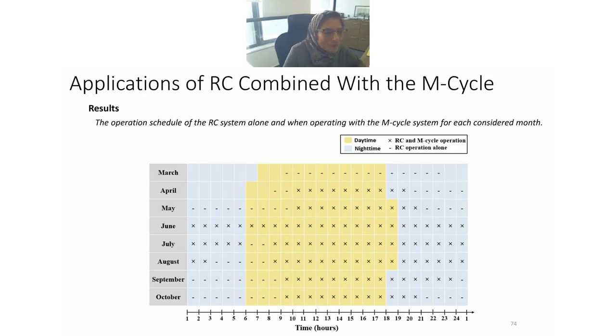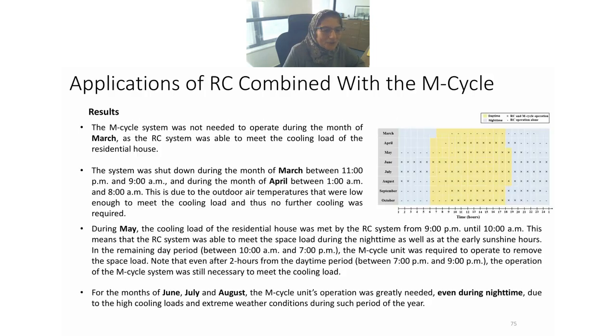In June, I cannot do without operating both systems all day. In August, it's the same. As we get to milder months, dependence on the M-cycle decreases. As a result, the M-cycle system was not needed during the month of March at all - that's the first finding. The system was shut down during March between 11 p.m. and 9 a.m., which is a lot of saving in terms of hours.